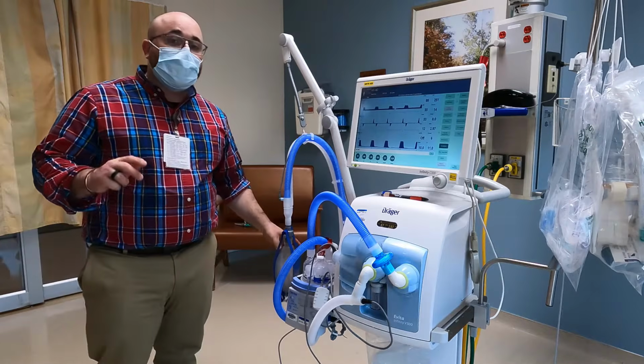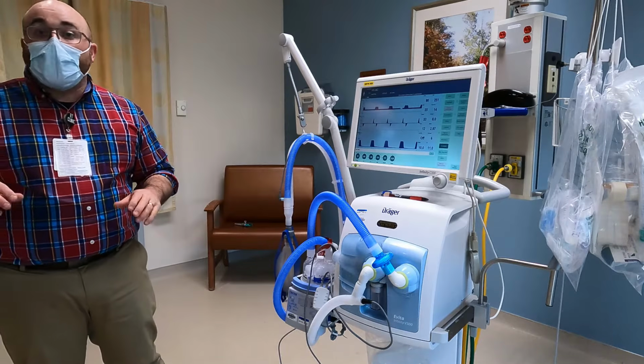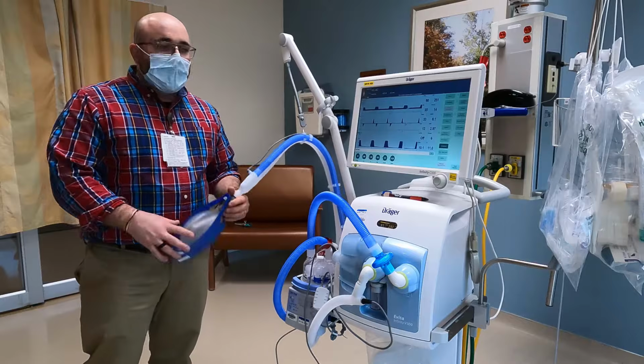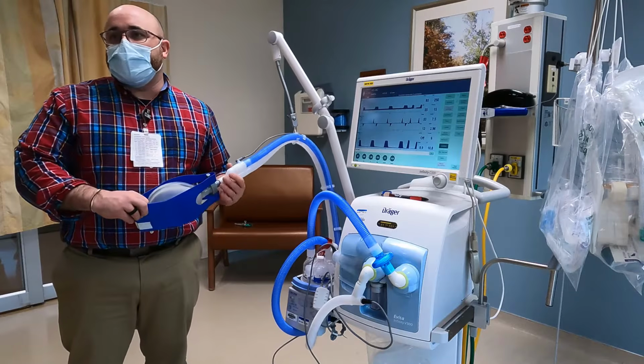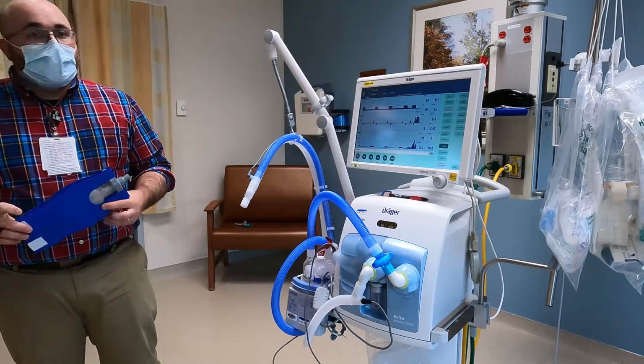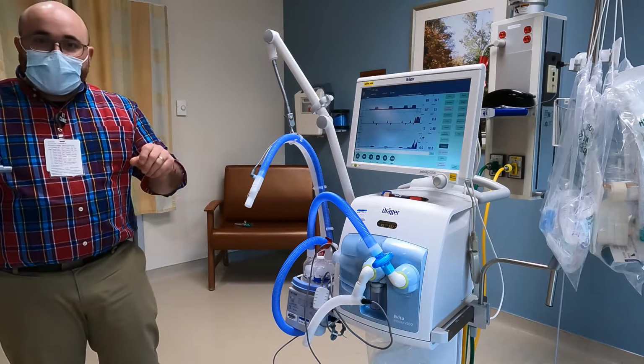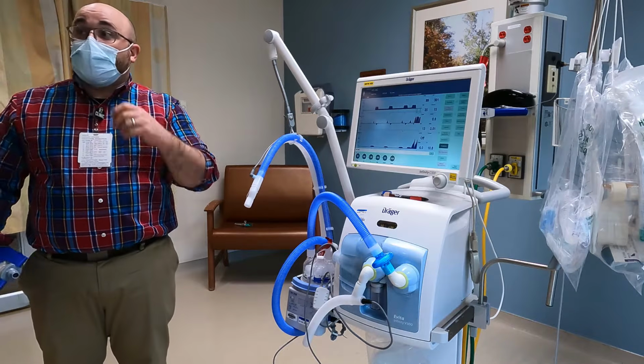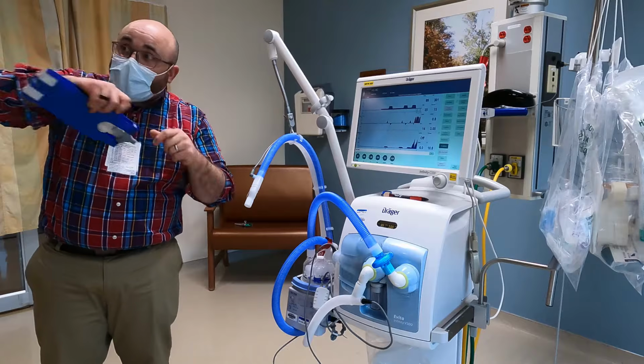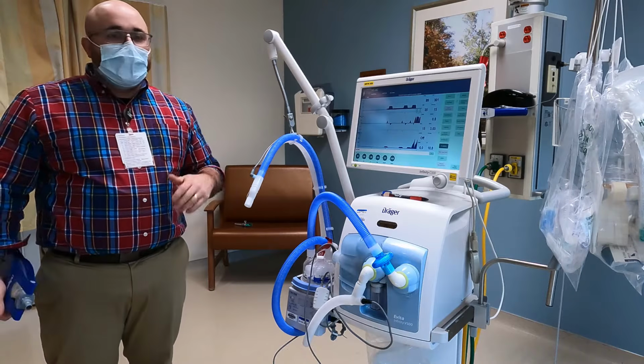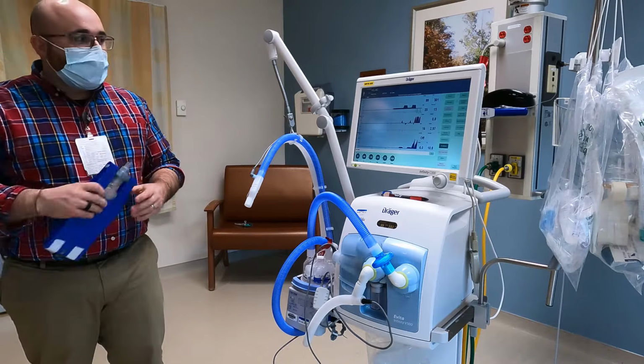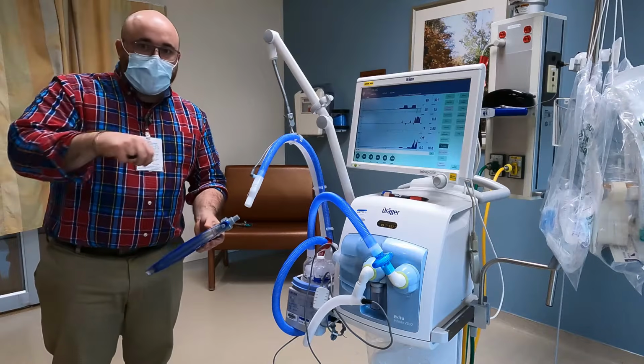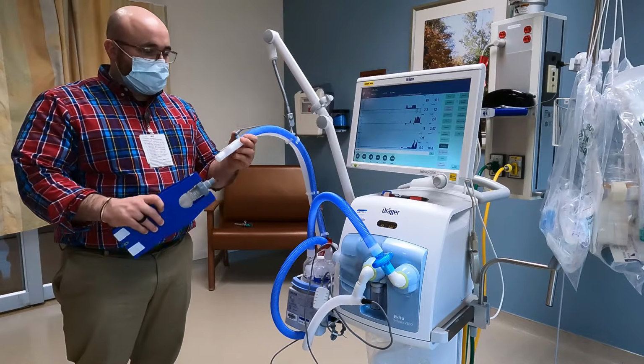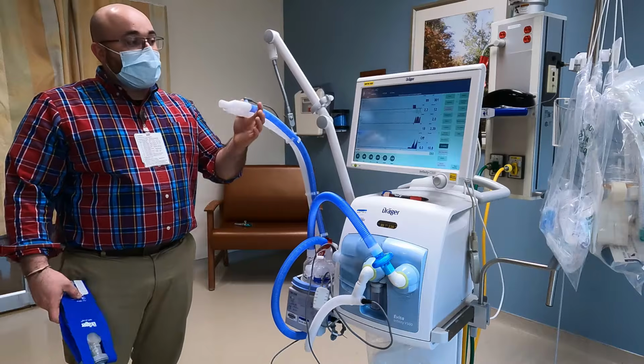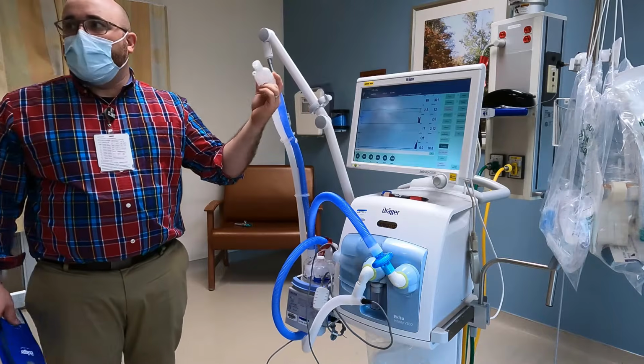So essentially what it's telling you is it's okay to disconnect the patient, or it's okay to suction the patient. Because when you suction a patient, it thinks it's disconnected. So years ago, before we had inline suction where you go down and suction, they had to take people off the vent, stick a catheter down, do it the old school way. Thank goodness we don't have to do that anymore. So they would take them off like this, they would suction them, causing a lot of nosocomial infections, VAPs and things. Once it's done suctioning, you see it's not alarming right now, no patient on.